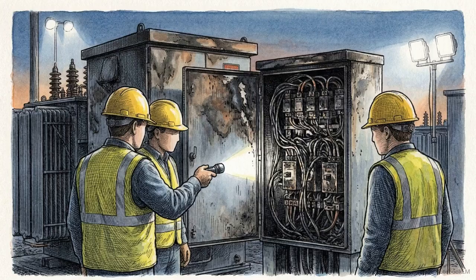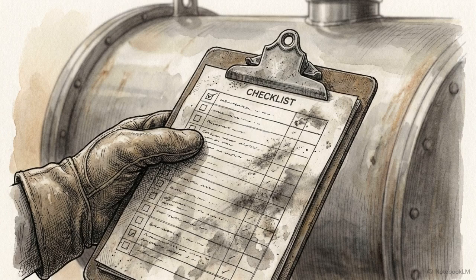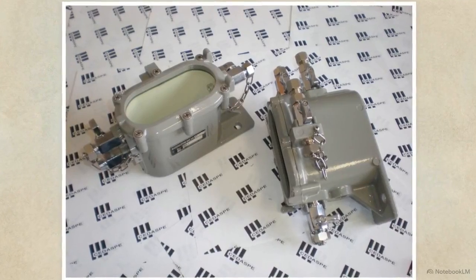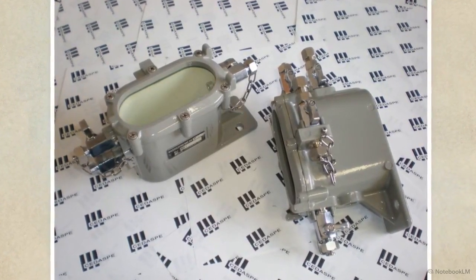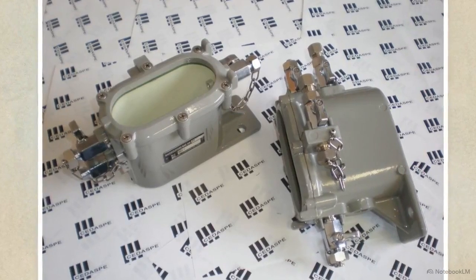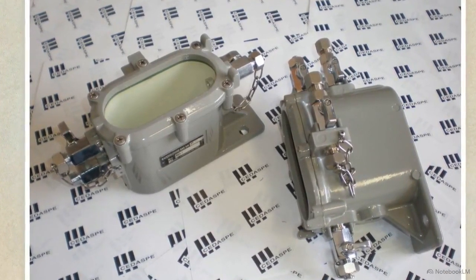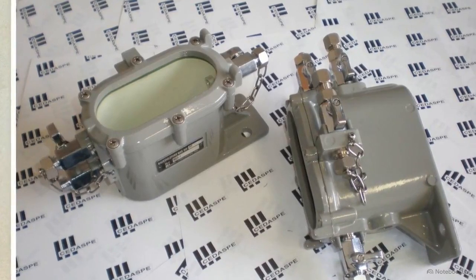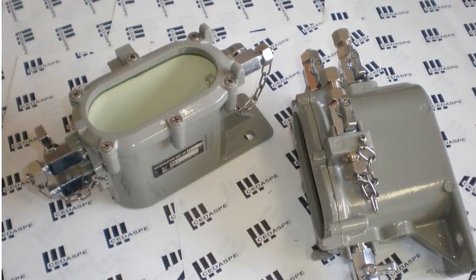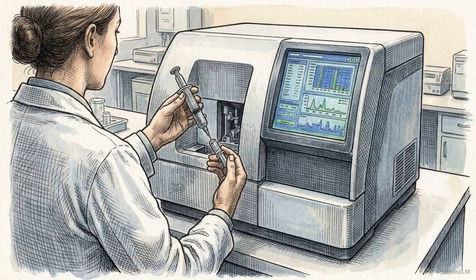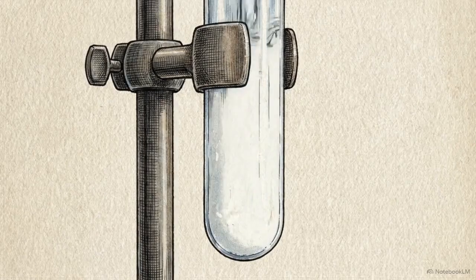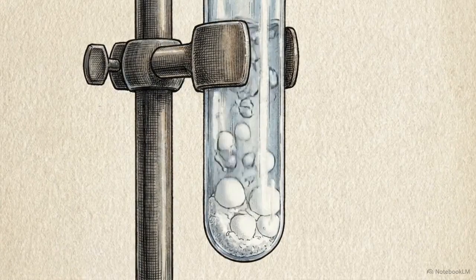Once the Buchholz relay trips and the transformer is disconnected, the emergency is contained, but the investigation begins. Engineers must determine exactly what burned inside the sealed, multi-ton tank. Because the relay trapped the fault gases, crews use a specialized sampling device to extract the trapped vapors without atmospheric contamination. Using precise metal petcock valves and inspection windows, technicians carefully bleed the hazardous gas into the sampler. This sample undergoes chemical forensics. The extracted gas is pumped into an analyzer, where it reacts to specific testing chemicals to form colored precipitates, identifying the exact point of internal failure.